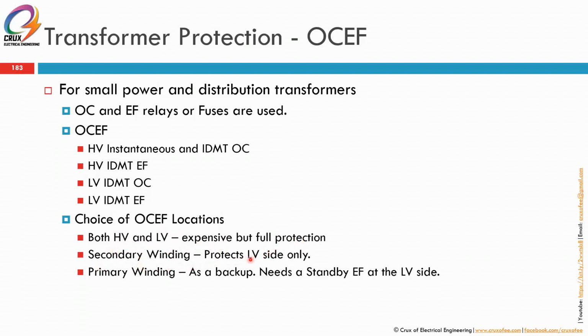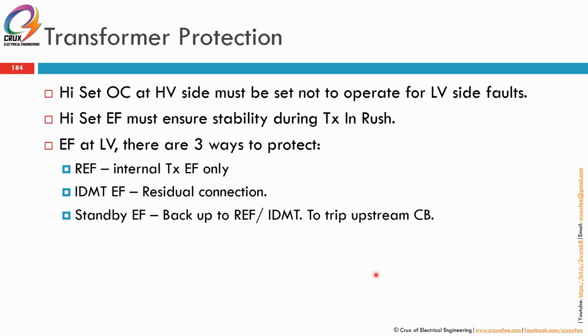Secondary winding protects LV side only. Primary winding as a backup needs a standby EF at the LV side. So we'll see what is meant by the standby EF. So high set overcurrent at HV side must be set not to operate for LV side faults. For example, if there's any fault on the secondary bus bar or any fault at the secondary winding. At the secondary bus bar or much downstream from there. So high set overcurrent must not be set to operate lah.